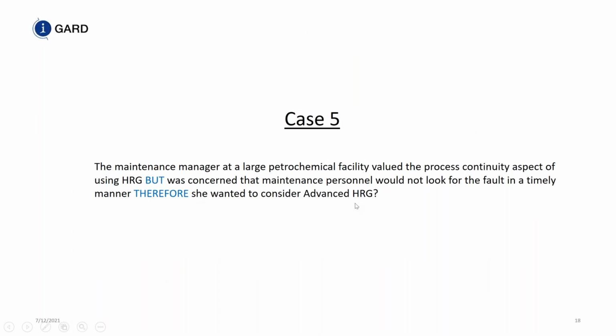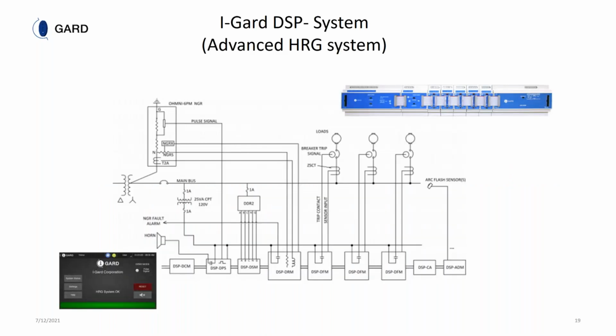So case number 5. A maintenance manager at a large petrochemical facility valued the process continuity aspect of the HRG system, but was concerned that maintenance personnel would not look at the fault in a timely manner. Therefore, she wanted to consider advanced HRG. Our high resistance grounding system, specifically the advanced high resistance grounding system, comes with an adjustable time delay. So if the fault persists for a long period of time, you can actually time it to trip out if the fault is not cleared in a time frame. So for example, when she requested this, she could put in a timer for 4 hours or 8 hours, and if the maintenance staff does not find the fault, the system would trip out.